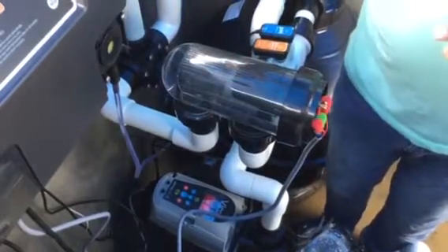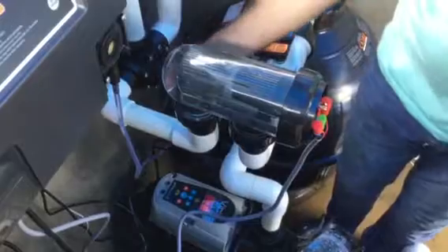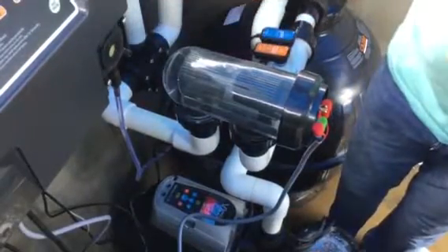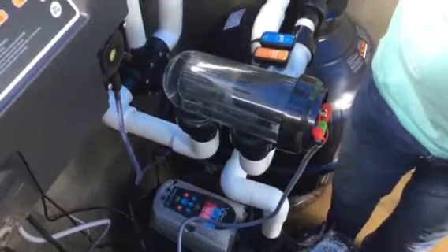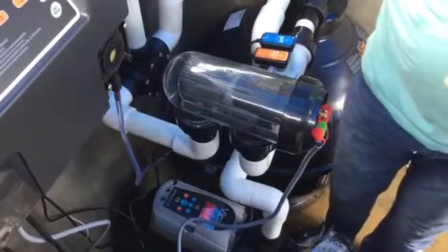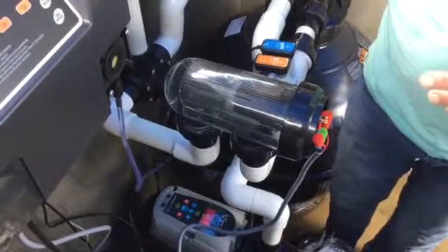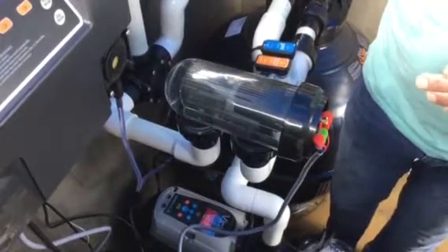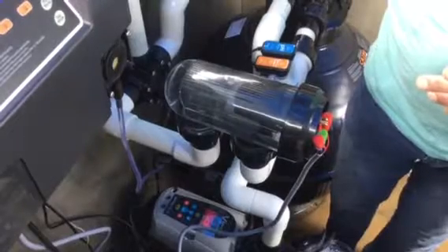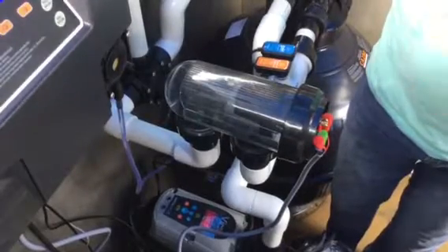But at any time you can change that, because you might say, well, look, we've manipulated our water flow here and really we don't like 2000 anymore, we like 1950. Then you can change this pump speed to 1950, and it'll always revert to 1950 each time in the future when it's running on low. And that's it for what's going on here. Awesome.